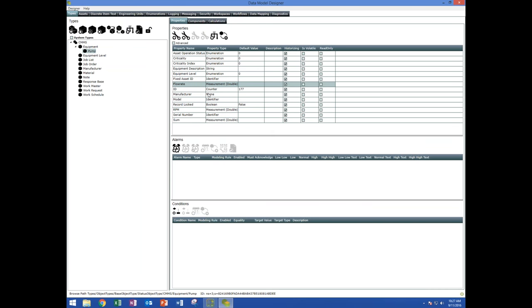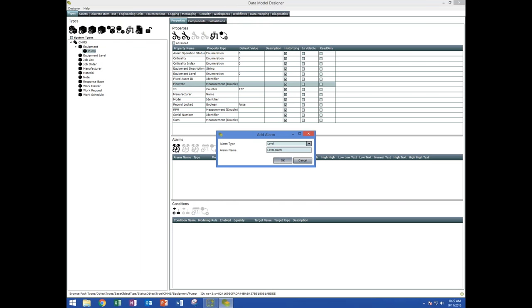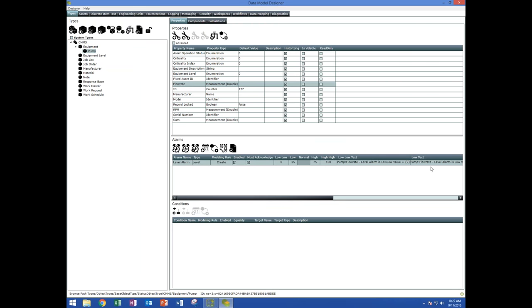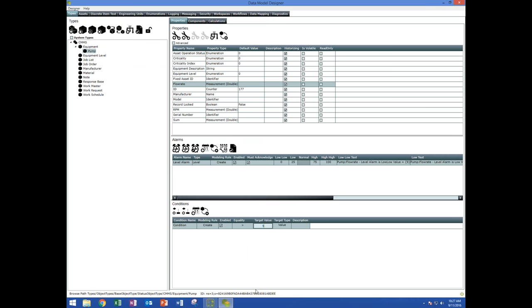If I want data logging on this flow rate property, I just hit that checkbox. As the values change on the flow rate, that value gets logged into the system. If I want to create an alarm for flow rate, I select my alarm type, create a new alarm, set the threshold values and messages, and set it up to be text messaged or emailed when the alarm becomes active. I can also create a condition — for example, if the value goes over 1,000, this condition becomes true and we can use it with workflow.